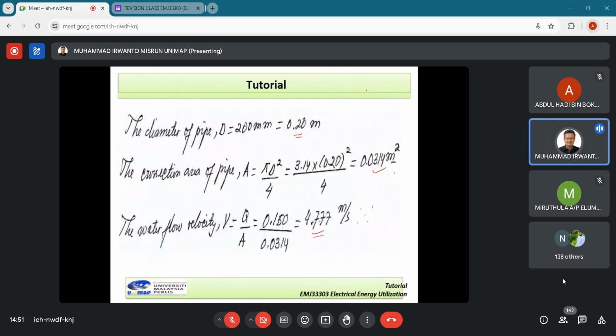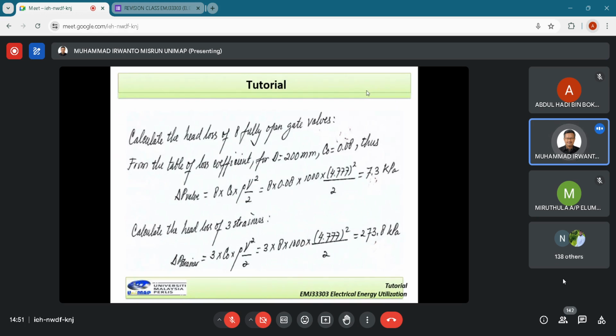First we have to find the value for the valve. The general formula for the valve loss, delta P valve, is equal to the number of valves multiply coefficient loss for the valve multiply rho multiply V power 2 over 2.